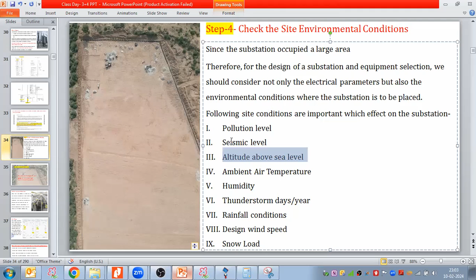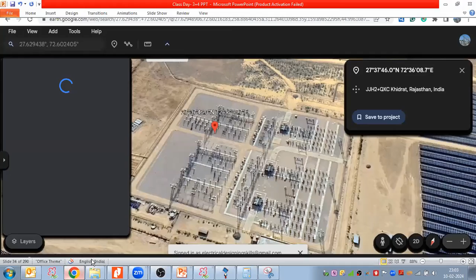So when you are at a site with a very polluted area, very little site space, and dust storms, in that case we do not go with AIS substations. Like here, if you see, we have AIS substations, but when space is limited and temperature is very high, we don't go with AIS - we go with GIS technology switchgear, the GIS type substation.